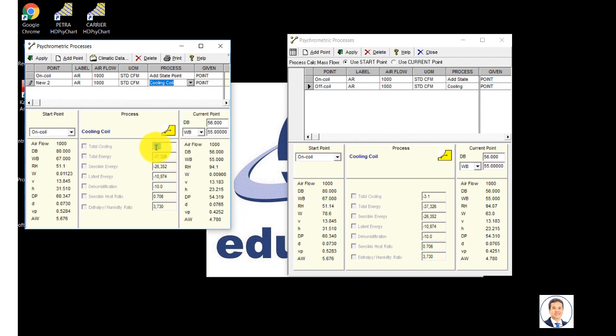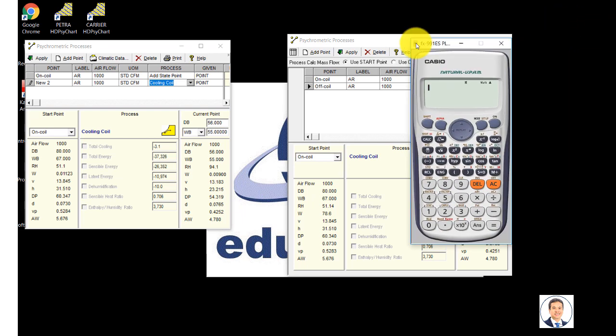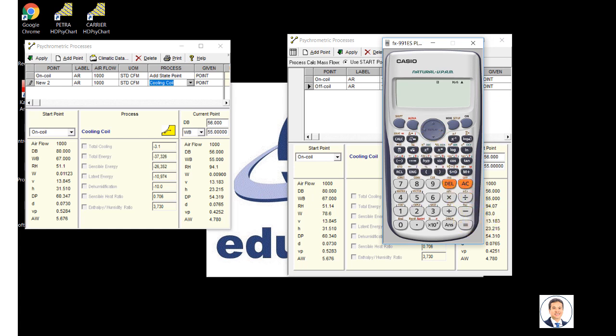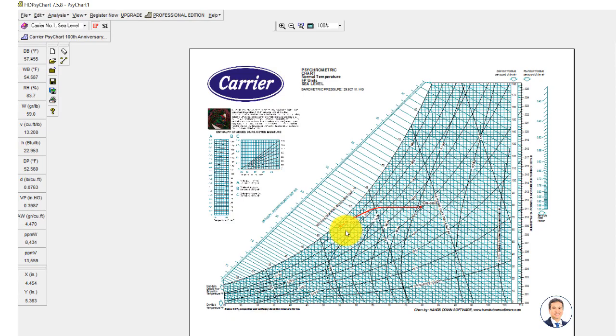By the way, maybe you got confused about this 3.1 value. This one is the cooling coil capacity, and I think this one is in tons. Remember that in terms of BTU per hour, we have 12,000 BTU in 1 ton. So that's just a conversion. 1 ton is equivalent to 12,000 BTU per hour. So this value is approximately 3.1, meaning this value is in terms of tons. So the cooling capacity in this process is 3.1 tons.